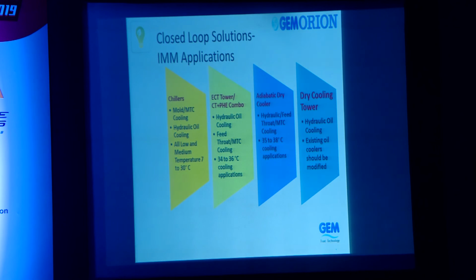can be both low and medium. Temperature setting can be 7 to 30. We can use chillers, or cooling tower plus PHE combination, or cooling tower and combination can be used for hydraulic oil, feed throat, but cannot be used for mold because we can get only temperatures of 34 to 36. Adiabatic dry again delivers temperature from 35 to 38. So use it only for hydraulic feed or throat, MTC cooling and other applications. And with dry cooling, in most of the cases, oil temperature can be maintained between 42 to 50 when people use synthetic. The only problem is if you want to use a dry cooler, we have to change the heat exchanger or the heat exchanger design approach. Maybe sizes we need to increase and directly give cooling water from the dry cooler to maintain the oil temperature.